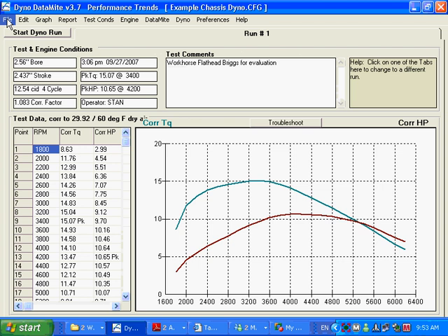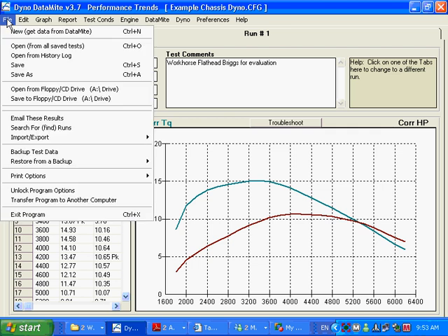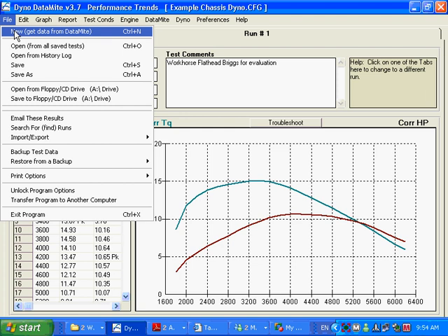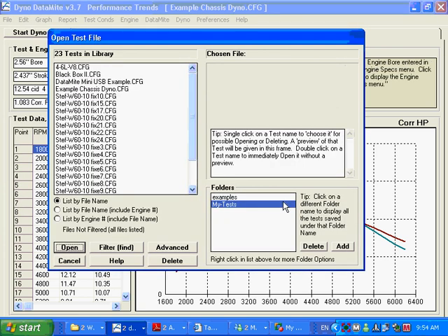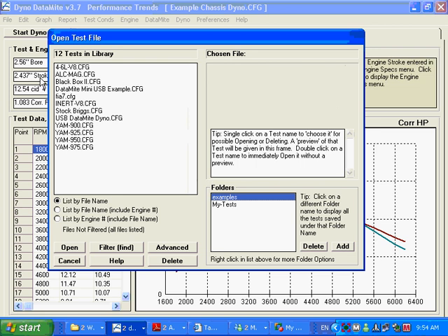So what you want to do, this is the better way to do, and this isn't told to you in those quick start setups, those loose pieces of paper that come inside your book, is you want to open an example test that matches the DataMite data logger you've got.